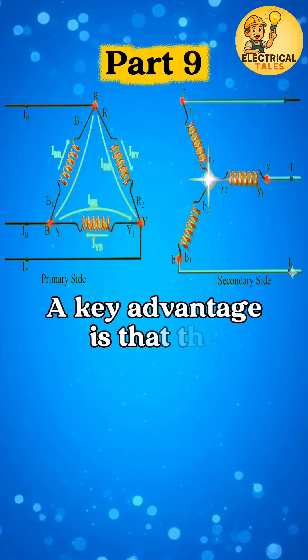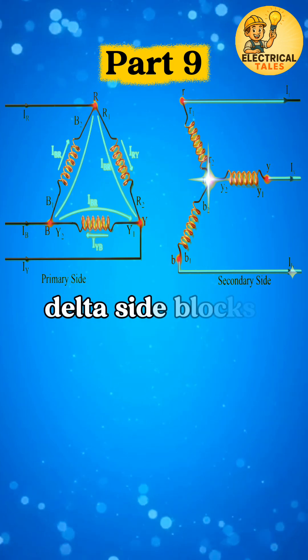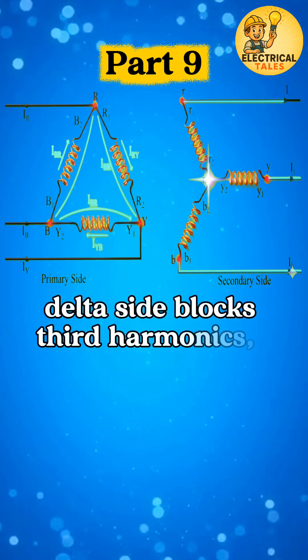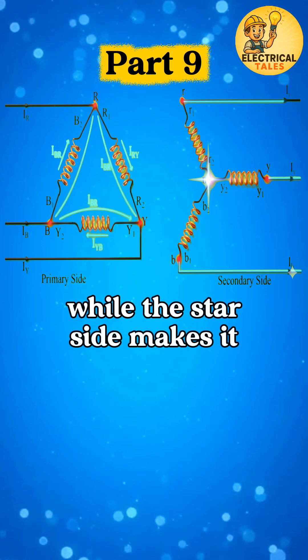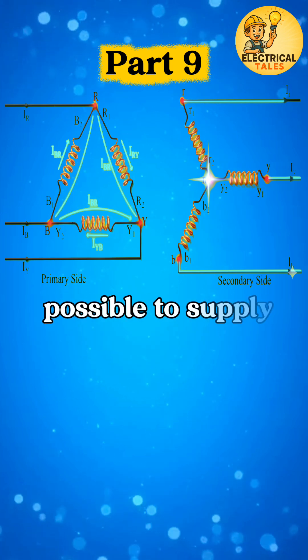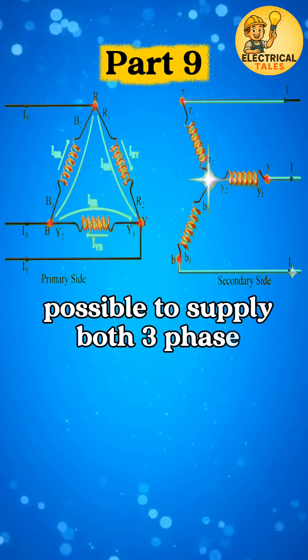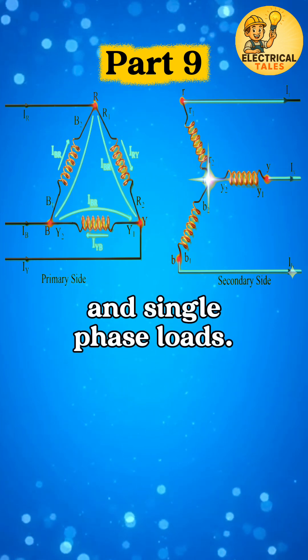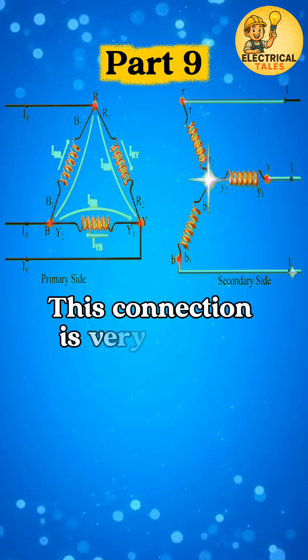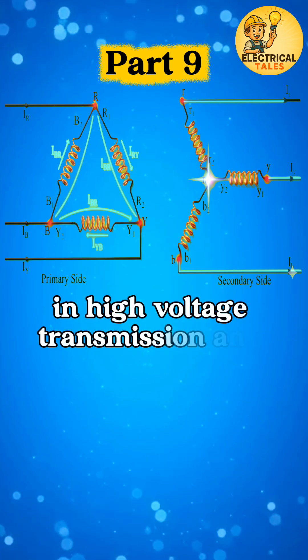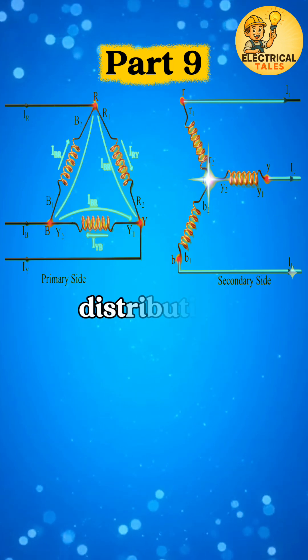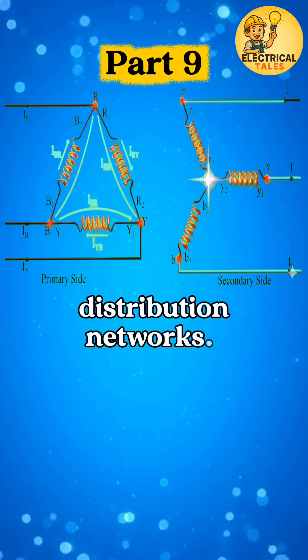A key advantage is that the delta side blocks third harmonics, while the star side makes it possible to supply both three-phase and single-phase loads. This connection is very reliable in high-voltage transmission and distribution networks.